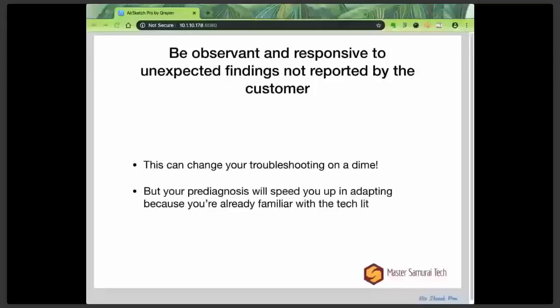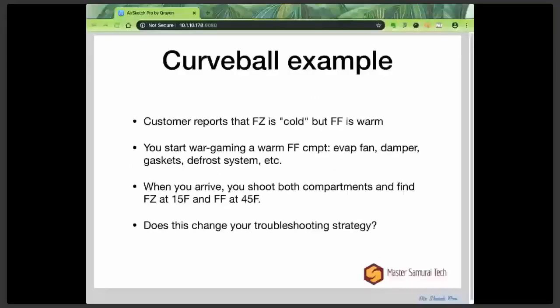Does this change your troubleshooting strategy? Yeah, sure does. Because now instead of just dealing with evaporator fans, dampers, and all this stuff, now I have to half split the problem. Do I have a sealed system problem? I should be asking myself that. Do I have a sealed system problem, or is it everything else outside of the tubing and the compressor?